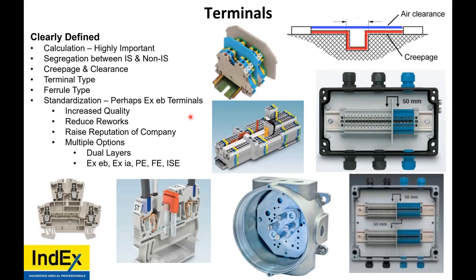It raises the reputation of the company, and you have multiple options for your EXEB or IA, or protective earthing, functional earthing, or your intrinsically safe earthing. You can have dual layers on all of these. You can have knife switches. The options are there, or you could just go with a post. But if you have regular terminals that are not EX and you put them in EXD, that is okay, but you have the chance of mixing your EX and non-EX terminals up. So you may put non-EX terminals into an EXE or EXNA box. That will be punch listed, and that will be a fault. Potential ignition source, yes?